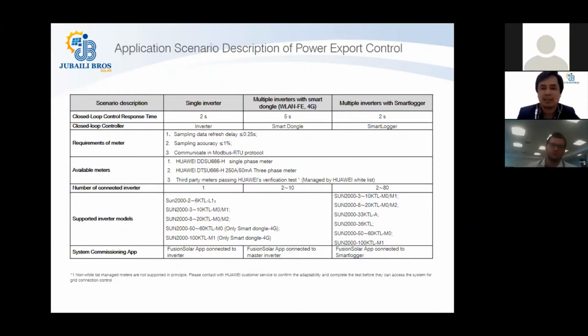When you are using multiple inverters with a smart dongle, this closed loop control will be 5 seconds. When you have multiple inverters with a smart logger, then you have 2 seconds. The closed loop control devices differ case to case. In a single phase, single inverter case, it is only the inverter itself. So there are still limitations in that. We will speak in detail.